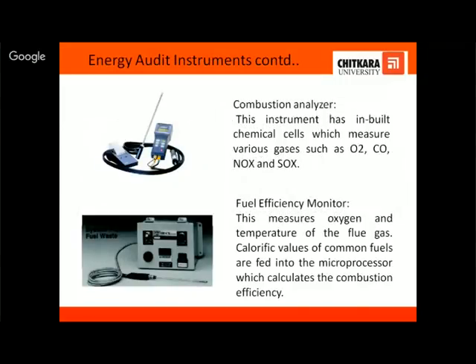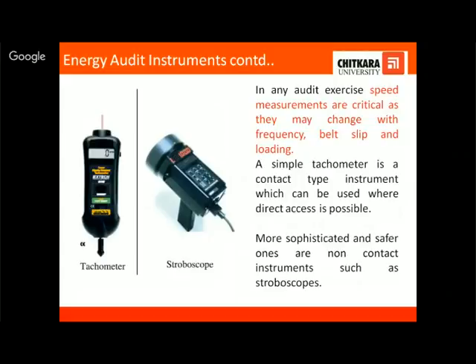Then there is a combustion analyzer. Then there is a fuel efficiency monitor. This fuel efficiency monitor measures the oxygen and temperature of the flue gas. Calorific values of common fuels are fed into the microprocessor, which calculates the combustion efficiency. Then speed again plays a very important role. We need to check the speed because it may change with the frequency or with the loading. The instrument can be contact or non-contact. The tachometer is a contact type. The stroboscope is a non-contact instrument which is used to measure the speed.